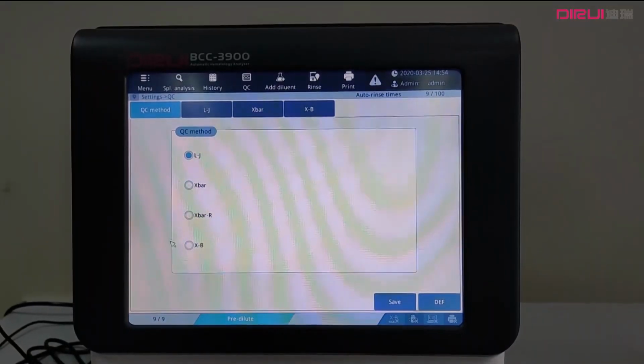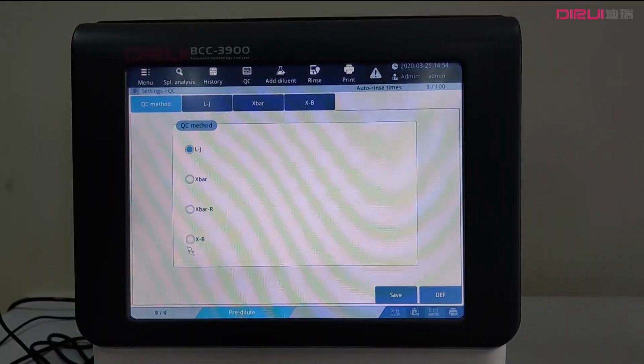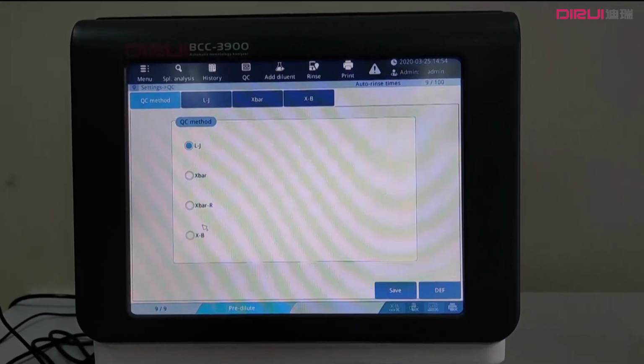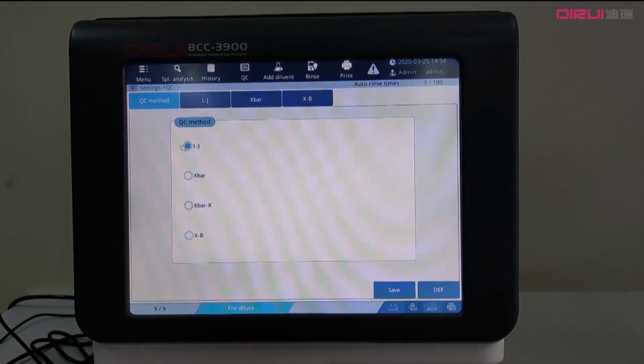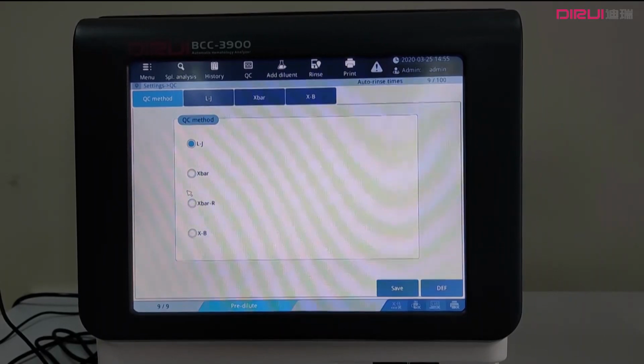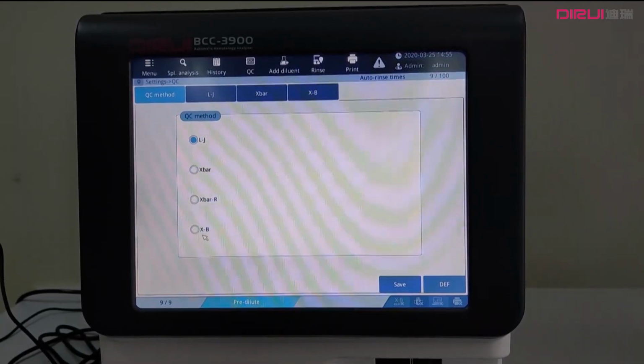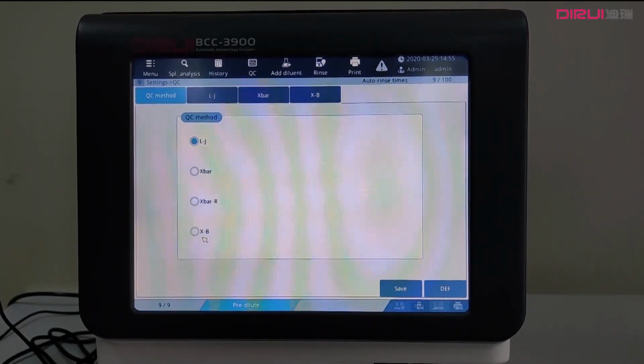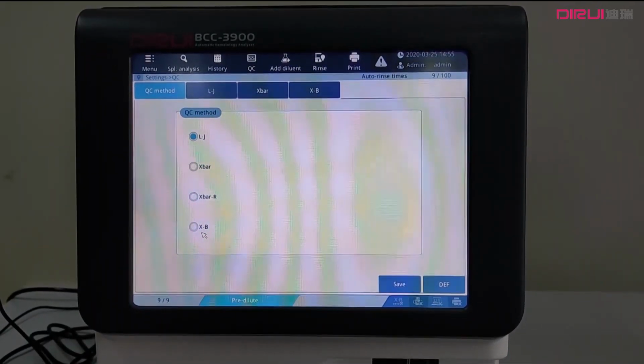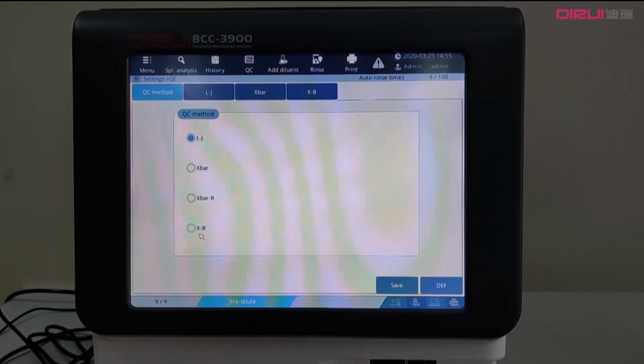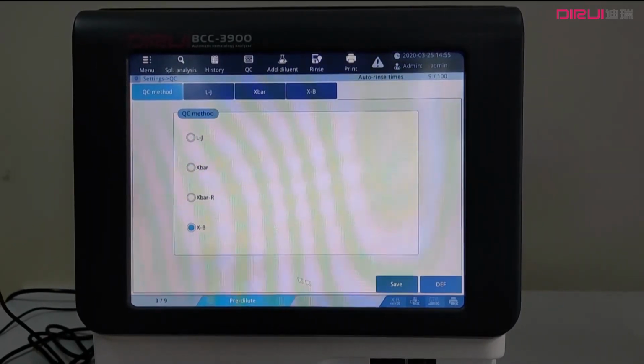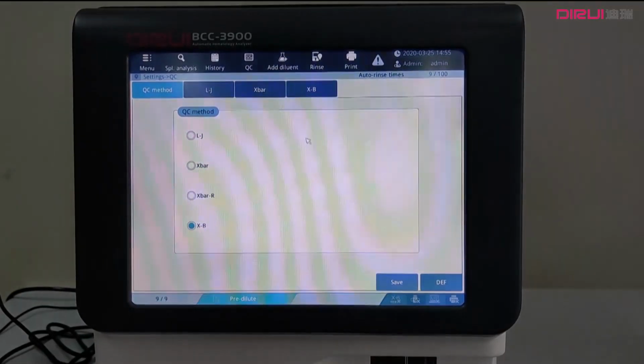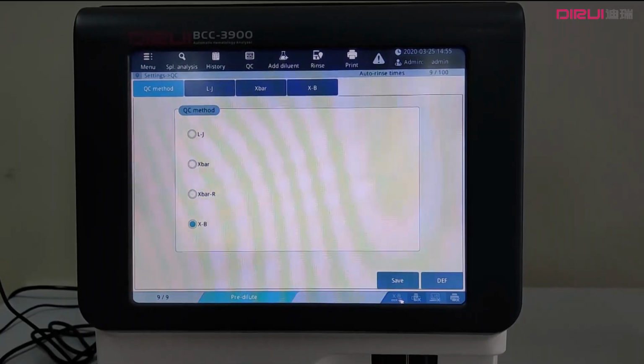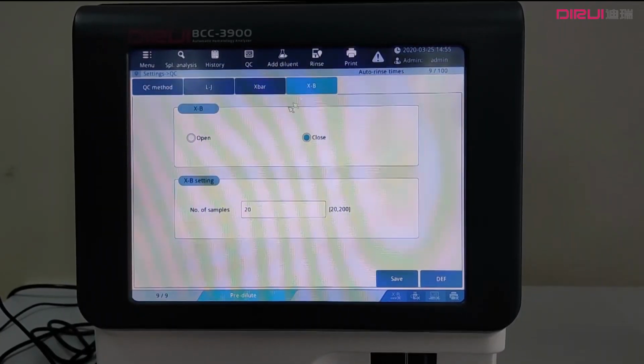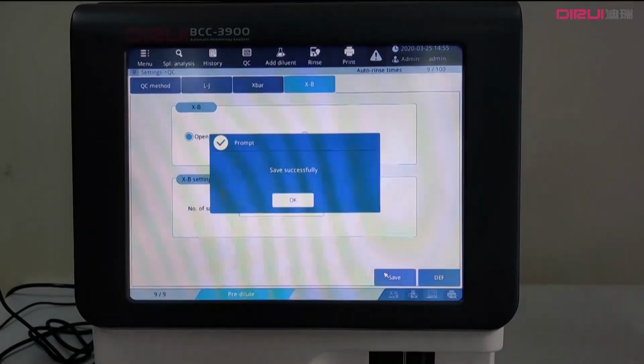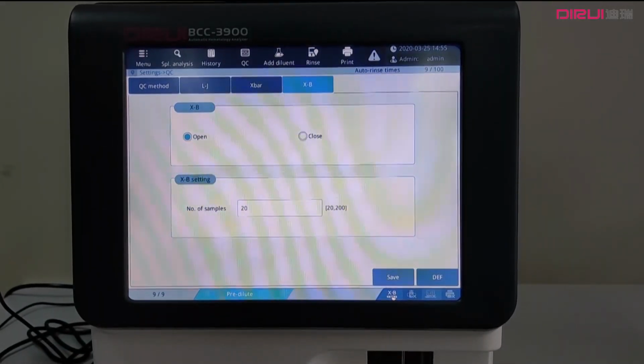The fourth QC method is XB. The difference between XB and the above three methods is that in all of the above methods we use quality control blood, and in this one we do not have to use quality control blood, but instead we use normal human blood, and that will be counted as our QC. So first select this one and press save and go. Right now you see the function is not turned on, so go to the XB tab, open and save, and now the XB function is lit up.